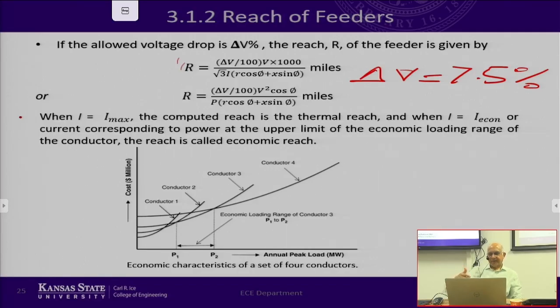Also keep in mind that the economic calculations use P based on the initial load, but load is growing at a certain percentage. So when you calculate reach, you must use the final value of the peak load, not the initial value. For economic calculation, you use the initial value; for reach calculations, you need the final value. That is very important.